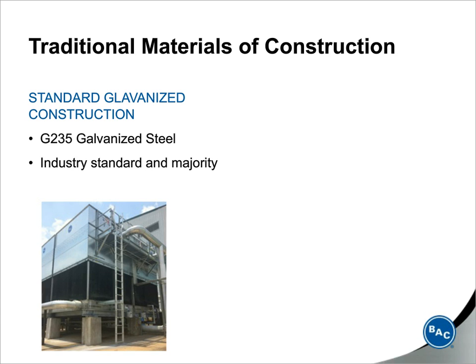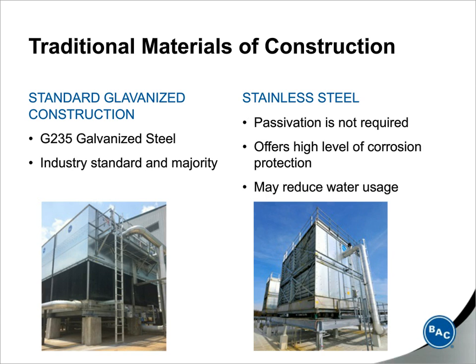Stainless steel does provide a much greater level of protection, but it does also add a lot more cost than a conventional galvanized tower. Stainless, or any material of construction that can provide higher corrosion protection than galvanized, does offer the opportunity to save water, since you can increase the cycles of concentration in the water and still have a very long-lasting unit, or extend the life of your equipment.